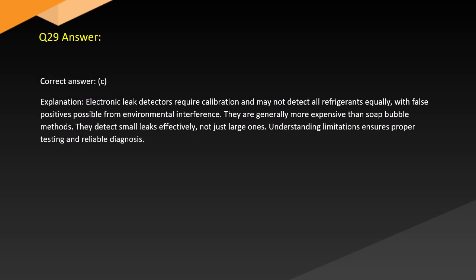Answer. Correct answer, C. Explanation. Electronic leak detectors require calibration and may not detect all refrigerants equally, with false positives possible from environmental interference. They are generally more expensive than soap bubble methods. They detect small leaks effectively, not just large ones. Understanding limitations ensures proper testing and reliable diagnosis.